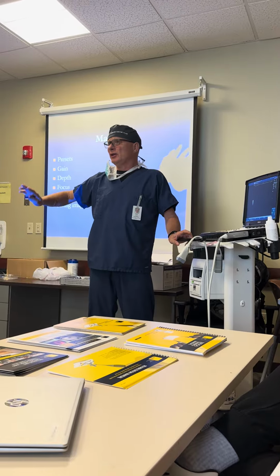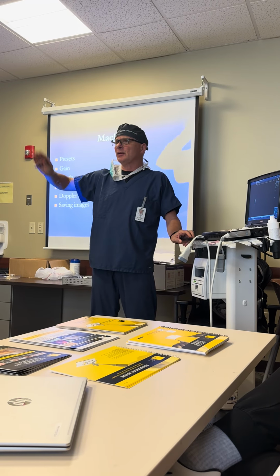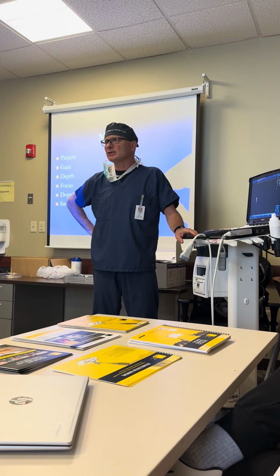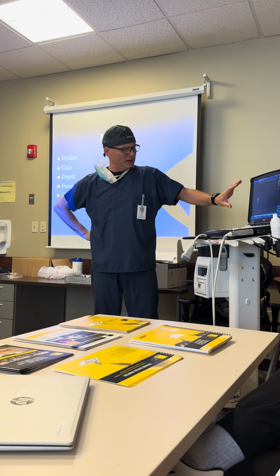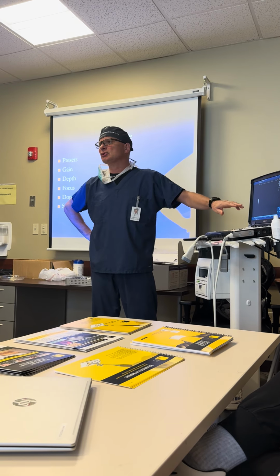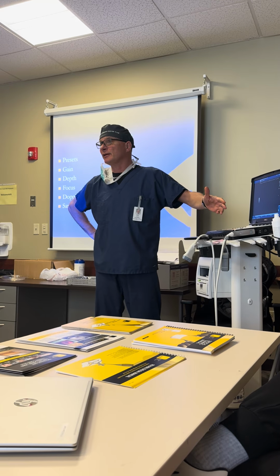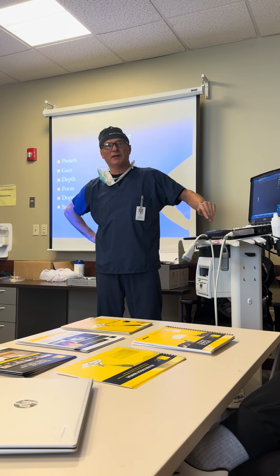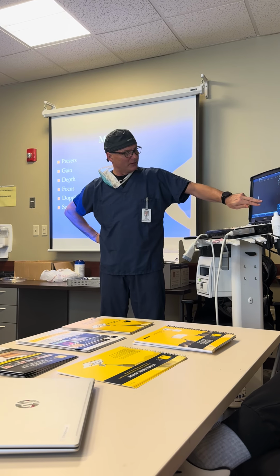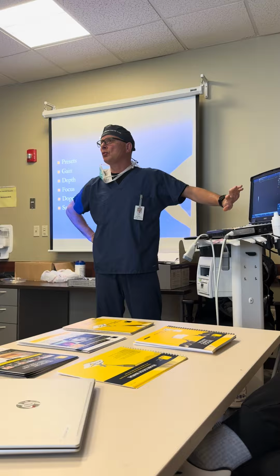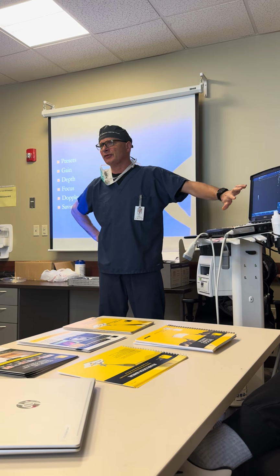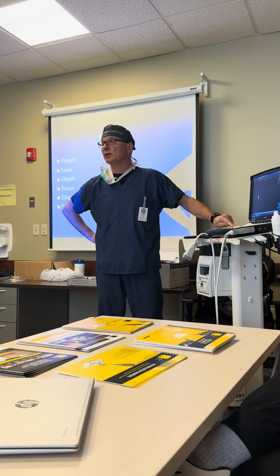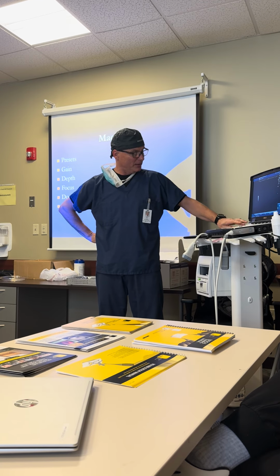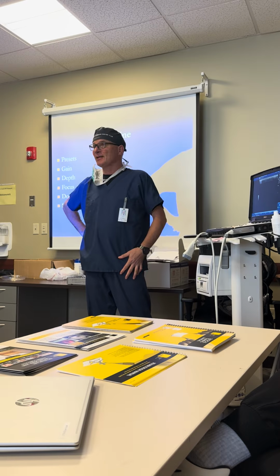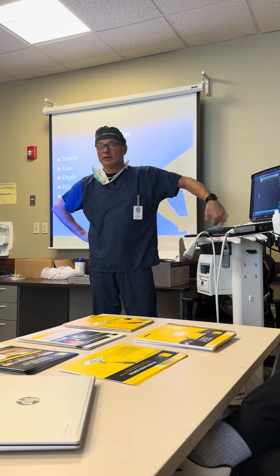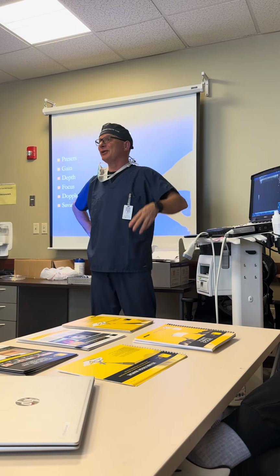It's a long story why we need this, in essence, because the speed of the ultrasound varies from patient to patient, and the preset gain that's in the machine is not perfect for every patient. So we can adjust, if the nerve I'm working on is in the bottom part of the screen, I might need more enhancement and more amplification in that. That's what I can do with this. So when you clean up the machine and they look like this, when this is pushed over to the left side, that segment is not even working.